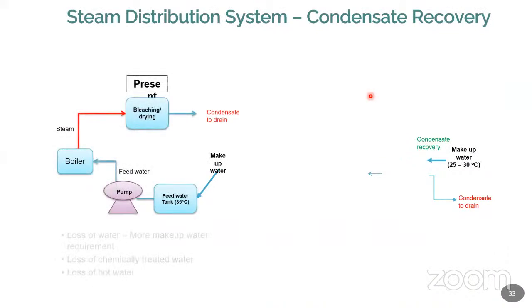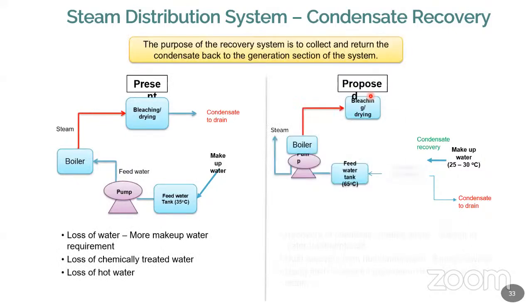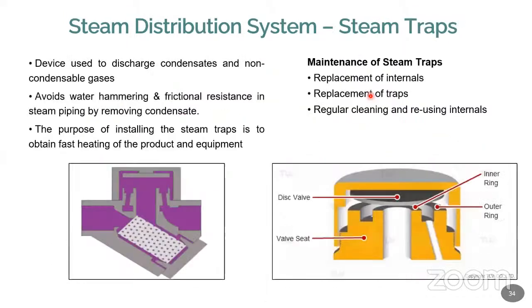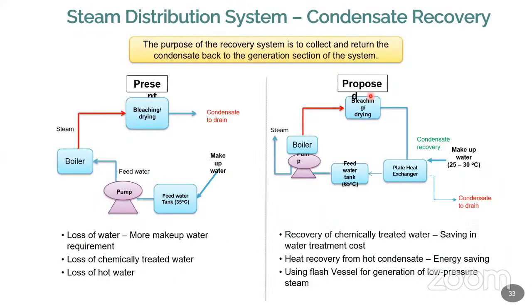Now you can see the steam distribution line. Of course, it's going to be almost the same, but from a different perspective, without the condensate water and with condensate water. This point we already discussed, but in a block diagram way, I have a pump that can be used to pump the feed water to the boiler. Now the feed water tank temperature is going to be 35, or atmospheric, ambient temperature. I'm adding the makeup water. So I have two types of water coming to the feed water tank. One is makeup water, or additional water. The second one is condensate water.